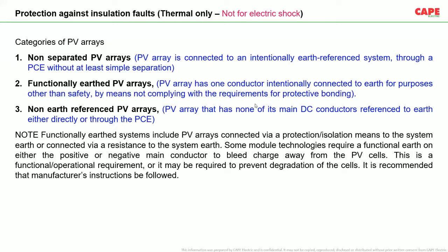Basically, there are three types of categories: a non-separated PV array system. Non-separated means the DC side and the AC side are not electrically separated. Electrical separation is possible either by a transformer or, nowadays, by semiconductor devices. So non-separated PV array means the DC side and the AC side do not have any electrical separation. Second, functionally earthed PV array. Third is the non-earthed PV array system. These three categories are made, and the fault protective measure against fire thermal effect has to be implemented based on the recommended measure for a typical application.